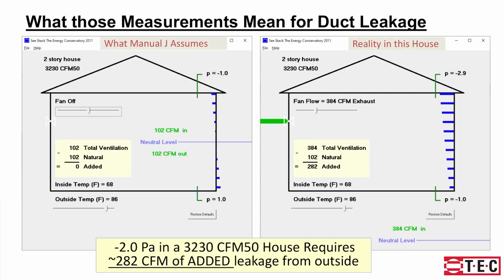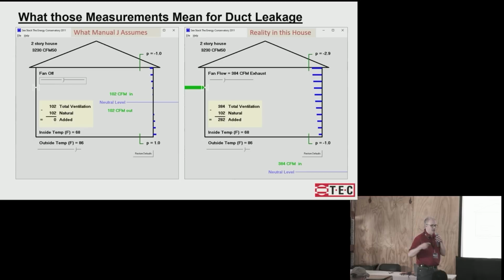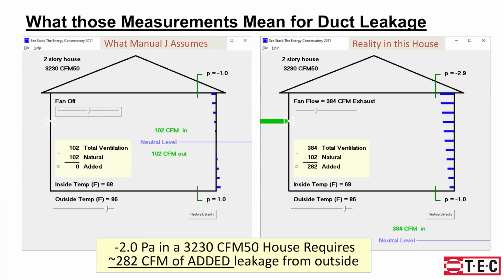flow, this fan flow can simulate what happens if you have duct leakage from the supply that's blowing out. That's going to do the same thing to the house as if you had an exhaust fan blowing out a certain amount of air. So if we know that the pressure changed by 2 pascals, in this case going from 1 to -1, that's a 2 pascal change. In order to get there, we have to change this exhaust. There has to be 384 CFM exhausting out the exhaust fan to cause it to depressurize by 2 pascals.